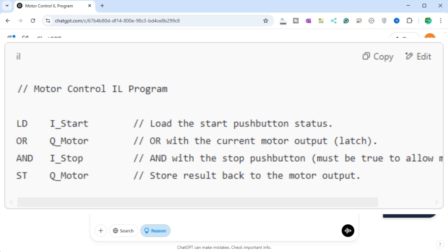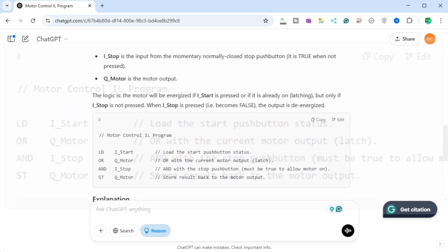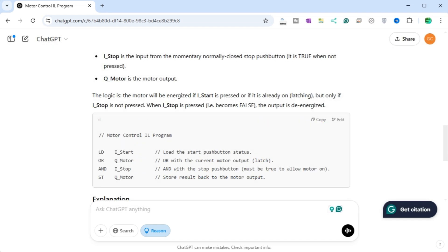The result is ANDed with the stop button status. Since I_stop is normally true, it will only be false, and thus de-energize the motor, when the stop push button is pressed. ST Q_motor. The final result is stored in Q_motor. This means the motor will be on if either the start was pressed, or it is already running, and the stop button has not been pressed. This IL code achieves the desired motor control function.